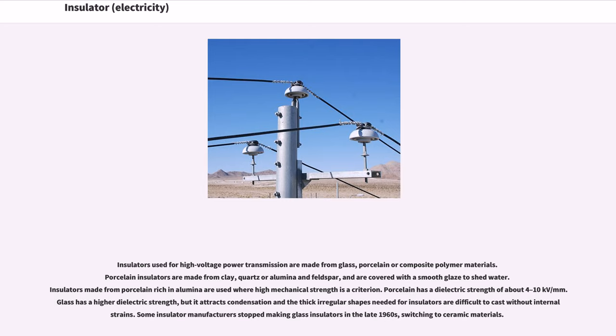Porcelain has a dielectric strength of about 4 to 10 kilovolts per mm. Glass has a higher dielectric strength, but it attracts condensation and the thick irregular shapes needed for insulators are difficult to cast without internal strains. Some insulator manufacturers stopped making glass insulators in the late 1960s, switching to ceramic materials.